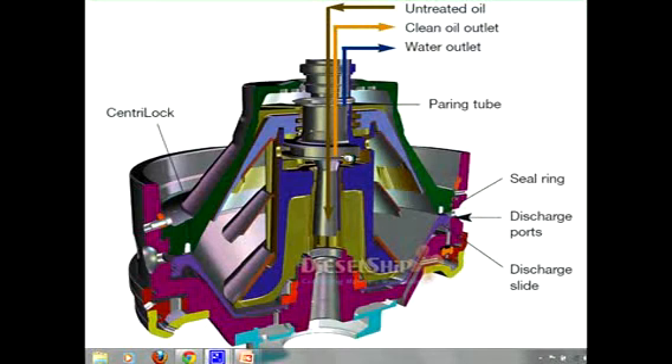The centripetal pump is stationary at all times. The fluid rotating at very high speed causes the pump to discharge clean oil through the clean oil outlet. The water which is collected at the interface point is pumped up by the paring tube — another stationary pump — and discharged through the water outlet.